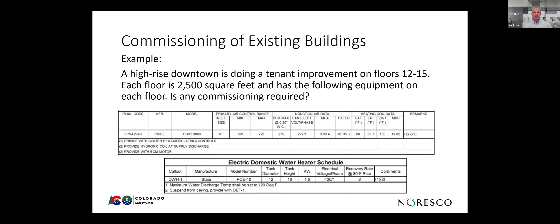Okay, so existing building commissioning, what is required of that? Really, I try to break it down to be as simple as possible. I mean, the code has several pages on this. 4 things. That's it. Code compliant commissioning for existing buildings only require 4 things. These are the 4 things: a commissioning plan, testing, adjusting, and balancing, functional performance tests, and then a report.